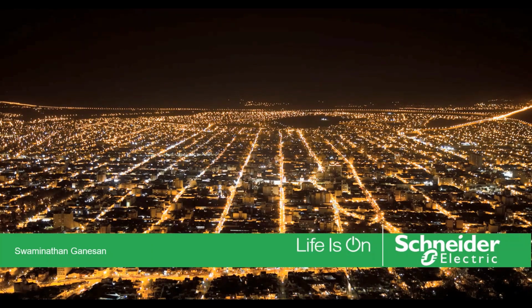What happened at one of the sites in Belgium? The circuit breaker blasted. There is one fixed contact and one moving contact in the circuit breaker. The moving contact was blown away from the chamber. Fortunately, no casualty. But that opened up a question of why it happened. Then we found out the reason.